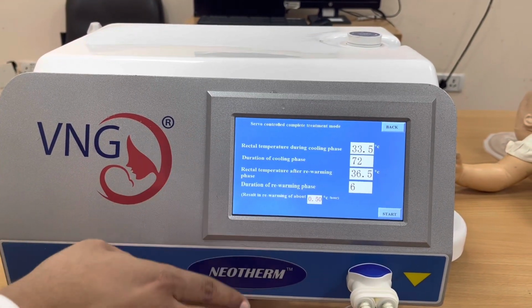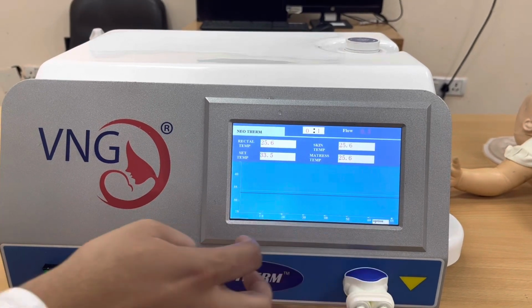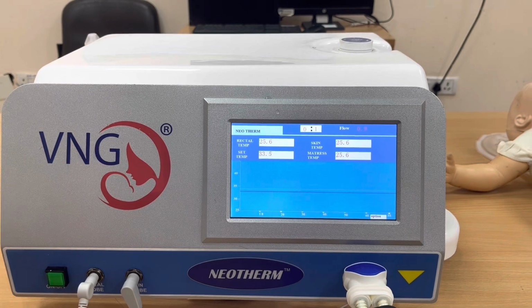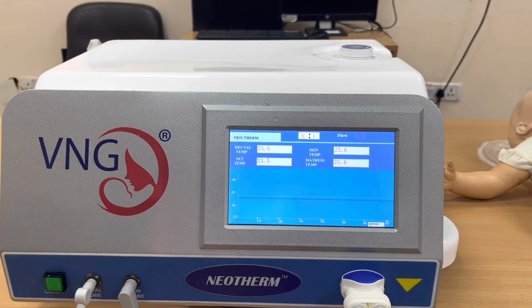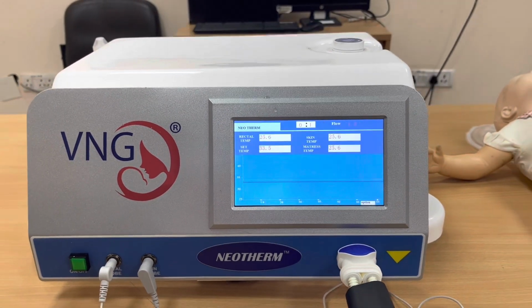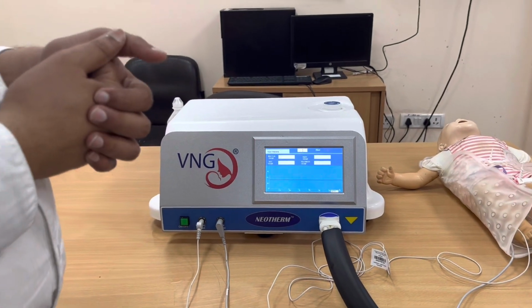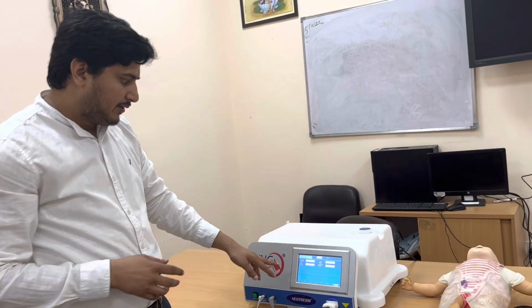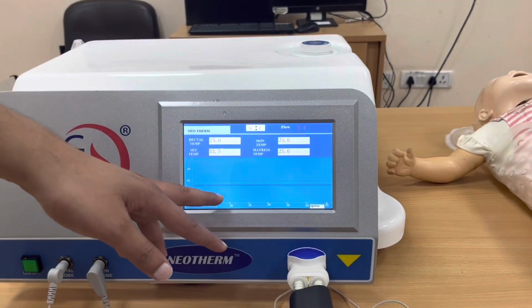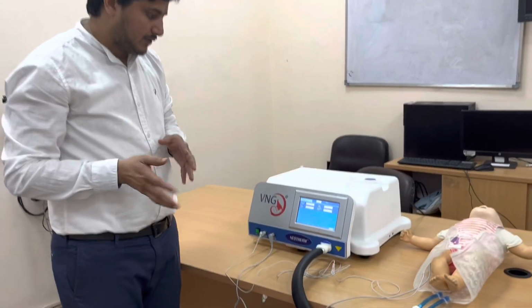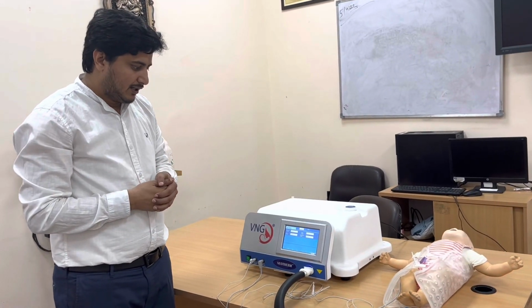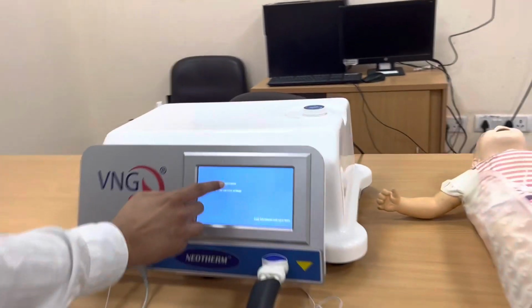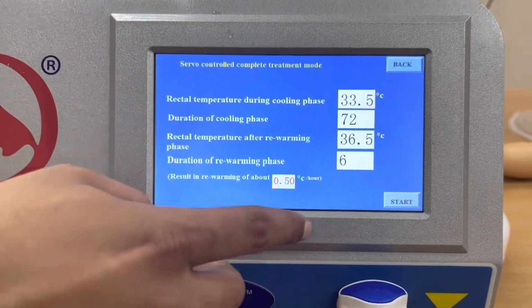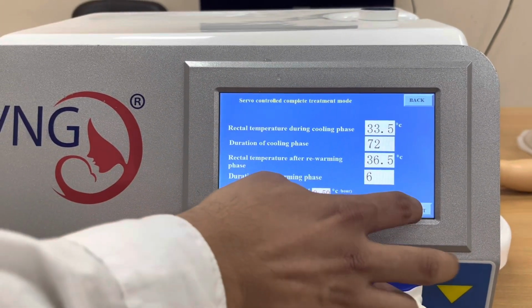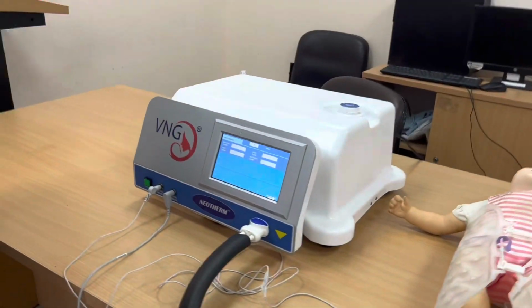So once we have entered all the temperature parameters, we need to click on the start button. As soon as we click on the start button, the device becomes functional, and ideally this device achieves the target rectal temperature within 25 to 30 minutes after initiation of the function. Here you can see that the machine is displaying the duration on the x-axis and the temperature on the y-axis. During the procedure, if you want to customize or make some changes in your settings, there is an option provided. Here you can change the current settings depending on your requirements at any point of time during the procedure. So now this device is fully functional and it is administering cooling for this baby.